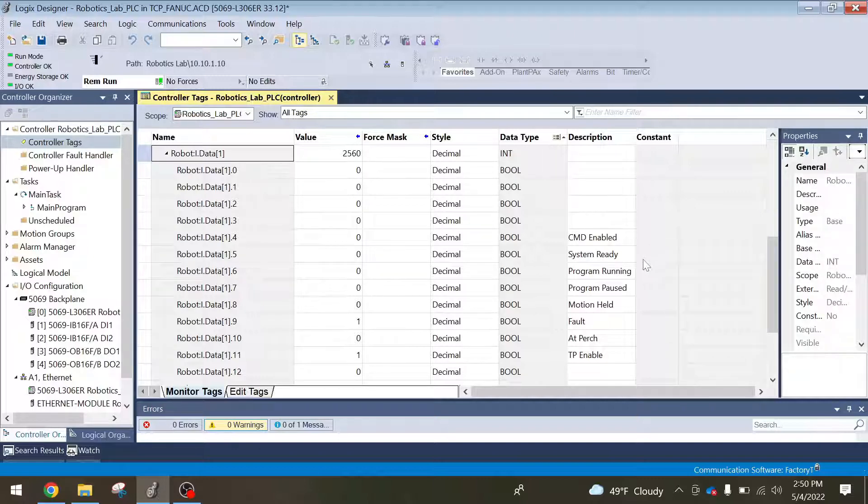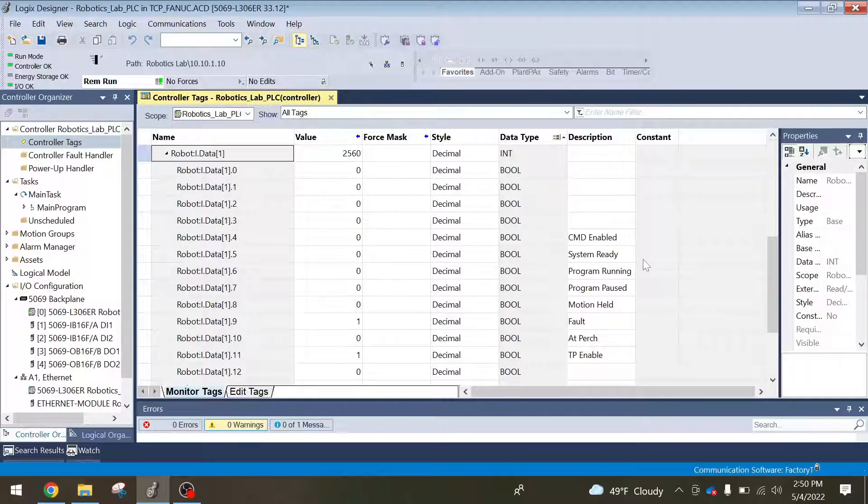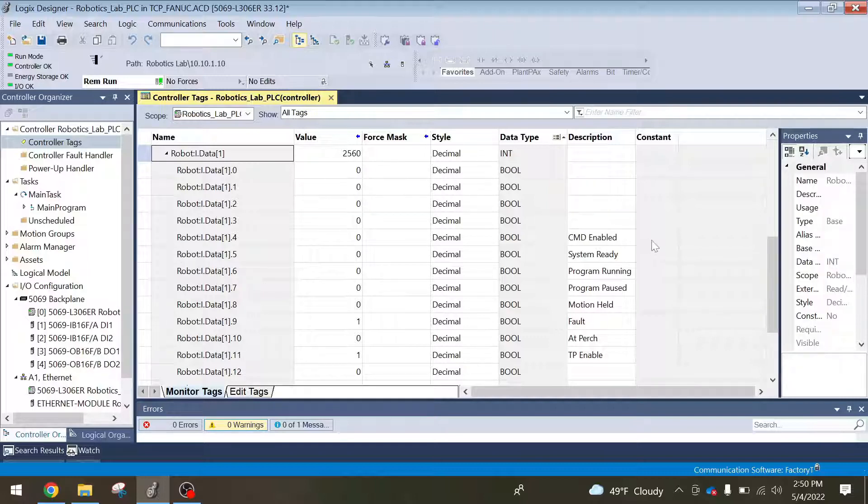System ready, so this is on when a certain number of bits are in an active state which tell you if the robot is ready to run. That's like if the robot's not faulted and the TP is not enabled in auto mode. And again, command enable, that means that the robot is ready to be triggered from an external device to start.